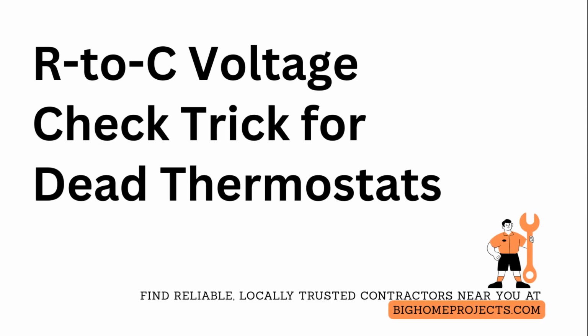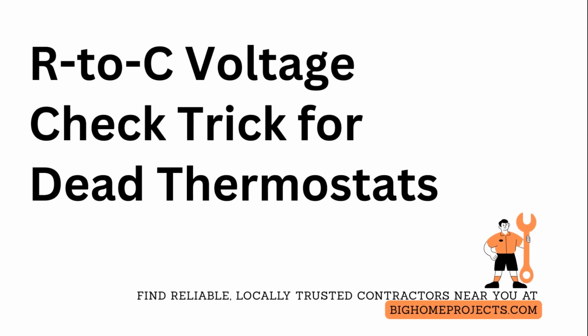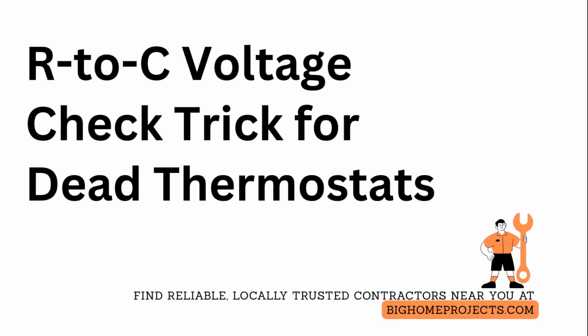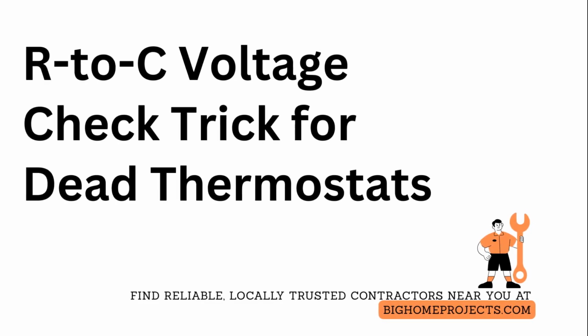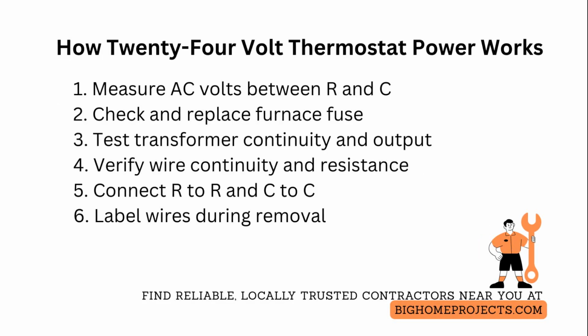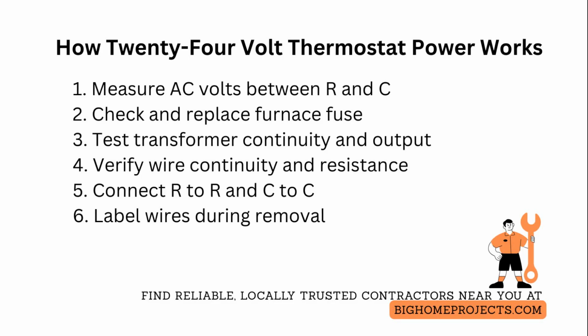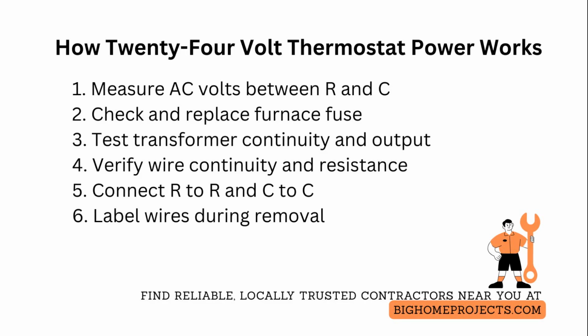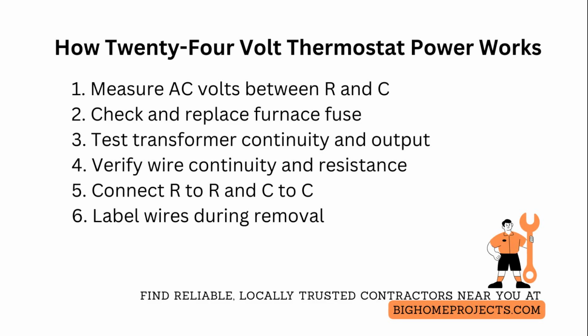How 24-volt power reaches your thermostat, and how to trace it quickly to fix a dead thermostat or faulty wiring. Power flows from the furnace control board R terminal as a 24-volt alternating current hot leg, travels through the thermostat bundle on the R wire, and returns on the common C wire to complete the circuit. To verify this without visuals, remove the thermostat cover, set a multimeter to AC volts, place the red probe on R and the black probe on C, and expect about 20 to 24 volts under no load.